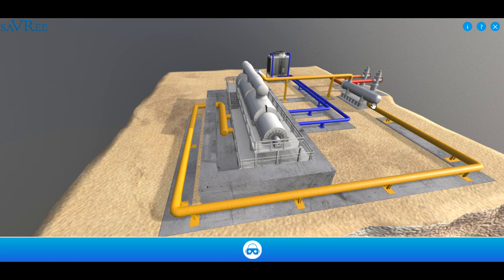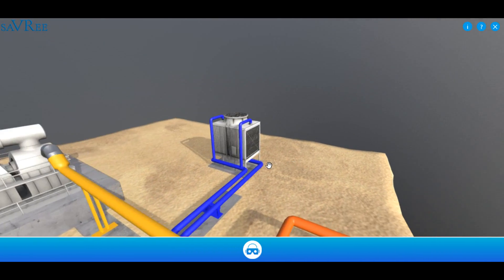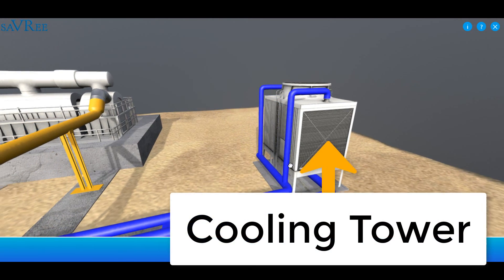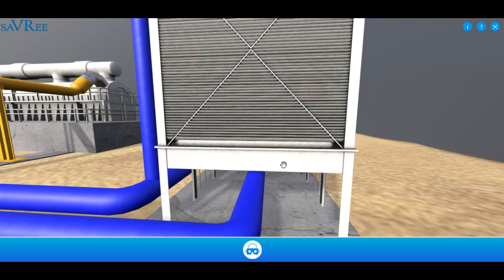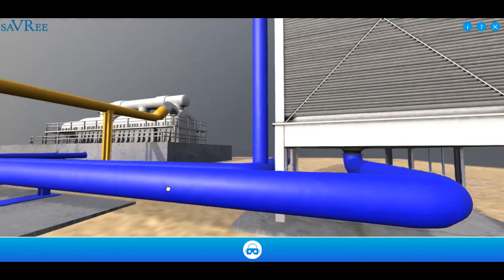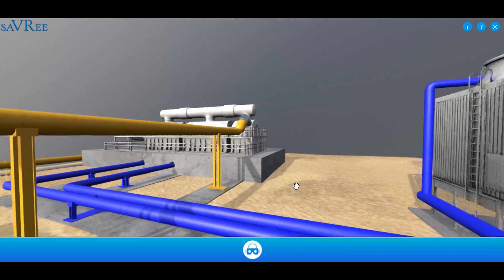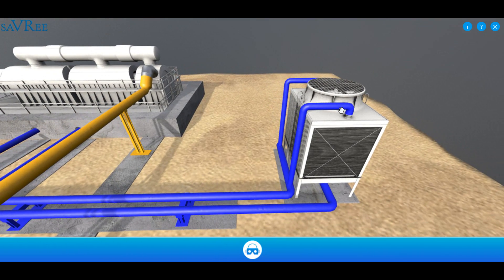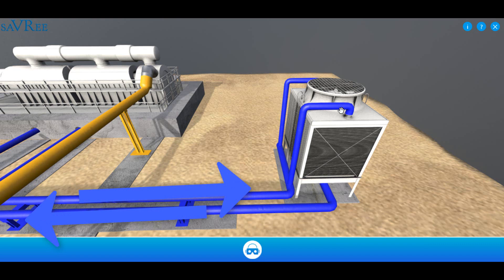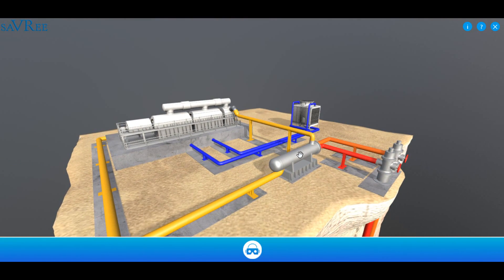You might ask: what cools down the working fluid and enables it to condense? We use a cooling tower to cool down the vapor. There's a cooling water circuit — water sits at the bottom of the cooling tower, is drawn out along this blue pipe, and carried to the condenser where it cools down the working fluid vapor. The warmed cooling water comes back out and travels along this pipe into the top of the cooling tower, where it's cooled back down by air, and then sent back to the condenser again. Essentially, we have a series of heat-exchanging operations.